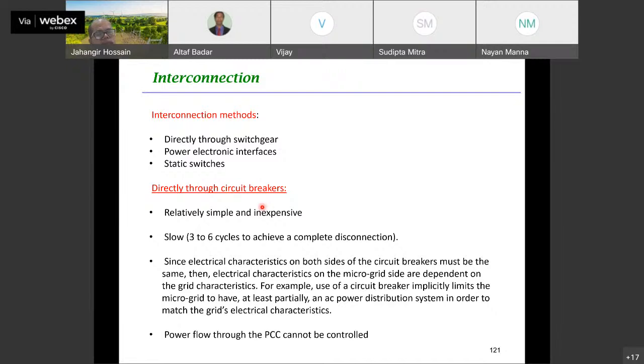The circuit breaker is relatively simple and inexpensive, but the speed of connection is slow - it takes about 3 to 6 cycles to achieve complete disconnection. The power flow through the circuit breaker you cannot control, and the electrical characteristics on both sides of the circuit breaker must be the same, so it's not electrically isolated.